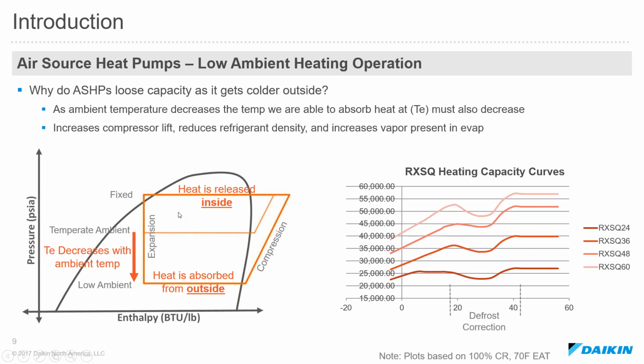And then you can also see in the bottom left corner of that red shape on the pressure enthalpy chart, the farther that corner gets away from that dark dome line represents the more vapor that's present in the evaporator. So vapor's already evaporated, it can't absorb any more latent heat, so it's just getting a free ride. Ideally we want just pure liquid in the evaporator so we can evaporate it all and absorb all that latent heat, but that's not the case. And it gets worse the lower we're dropping that temperature. So it's just increasing the pressure drop in the evaporator and getting a free ride.